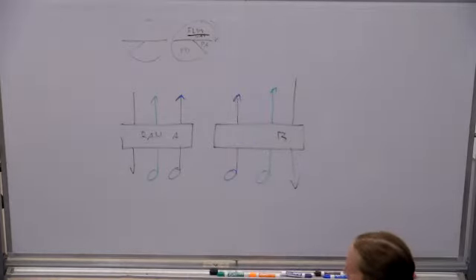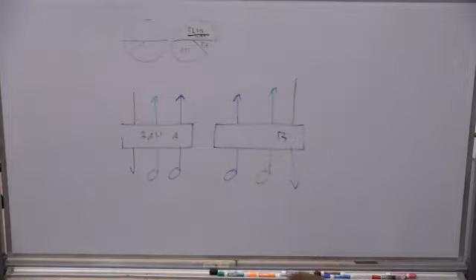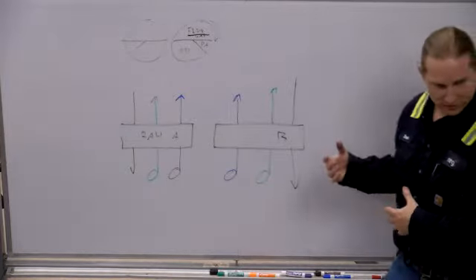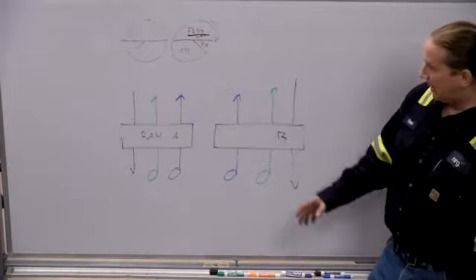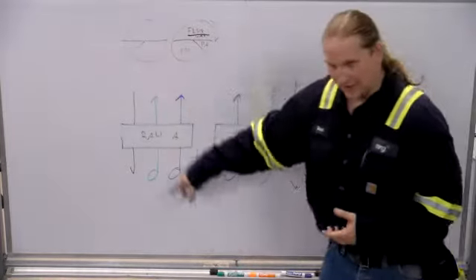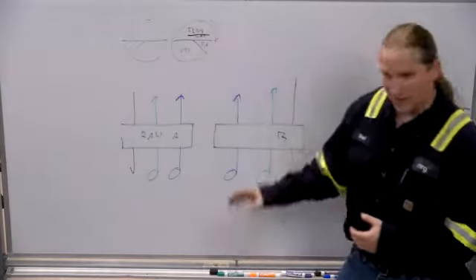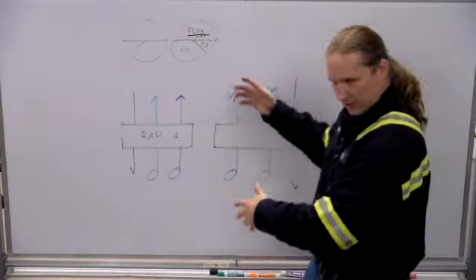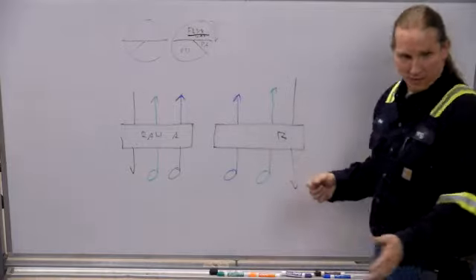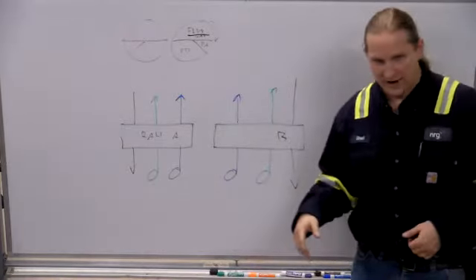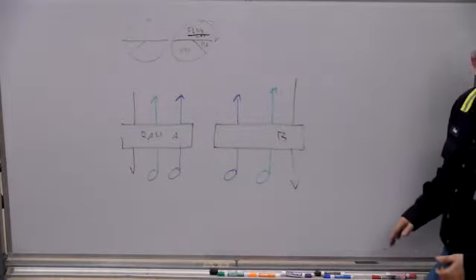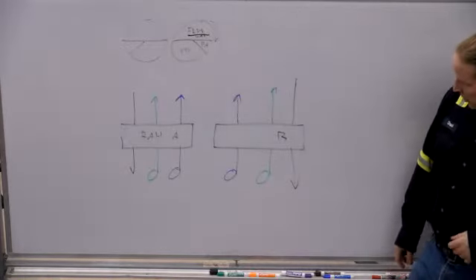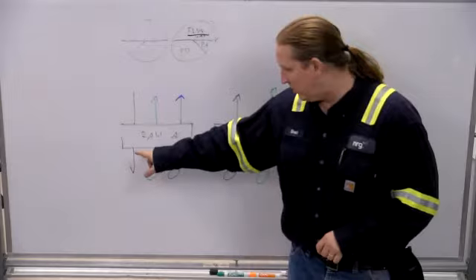So something you have to worry about on your rotary air heaters is this is upstream of the scrubbers, upstream of the SO2 control, the SDAs. So there's lots of sulfur dioxide in this gas. And if you cool it off, you have that dew point issue. And that cold sulfur dioxide will go to the metal, and then it will form sulfuric acid, and then it will eat up your ductwork. And then eventually you'll have holes so big that your ID fan can't keep up. And then you're going to have to derate the unit until you hunt down all these things and fix them.